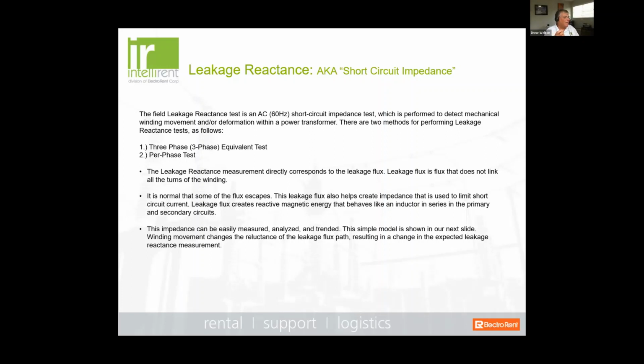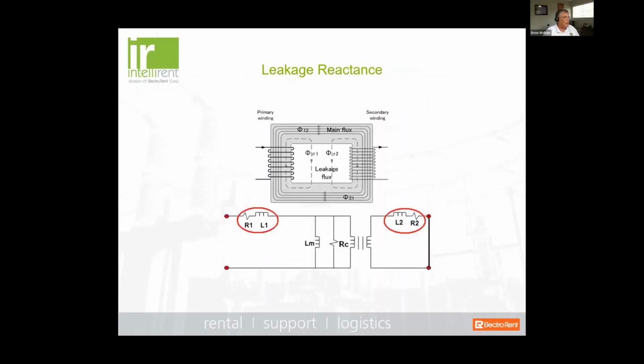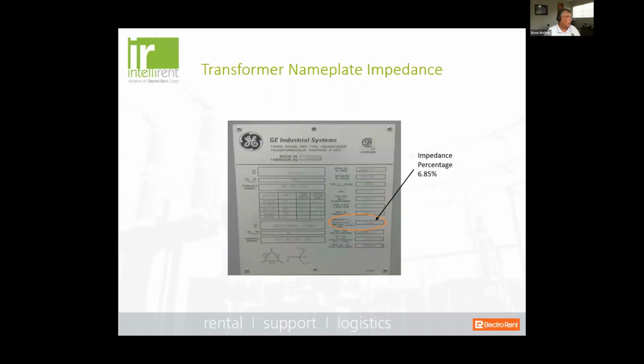So that impedance can be easily measured, analyzed, and trended. Okay, and we can see here that we have a simple model of your RL circuit on how flux is cut through the transformer, the primary and the secondary winding. And then here's your main flux, and then here would be your leakage flux between the windings. And this is, of course, normal.